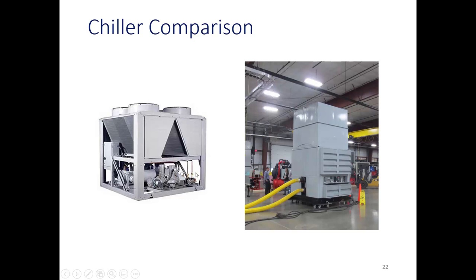So here's an example, just a chiller comparison. Here's the kind where you basically just have the frame. And like I said, a lot of times some of that stuff is just completely visible. If your exhaust fan is on the top, it's not enclosed in any kind of significant casing. It's completely open to the environment. So this would be an environment where there are no neighbors that you're concerned with. It's a very industrial setting. You don't care about the noise. And then on the other end, where you have a really critical environment.